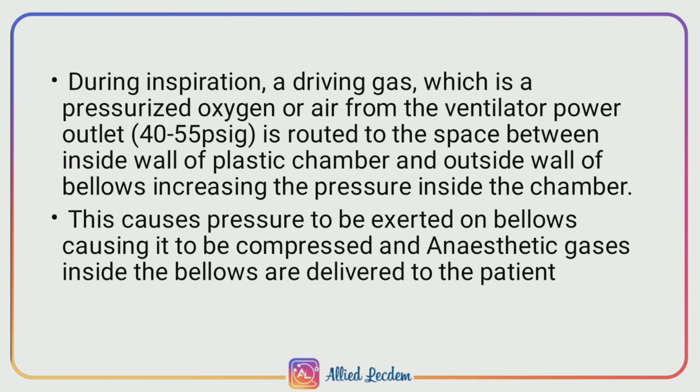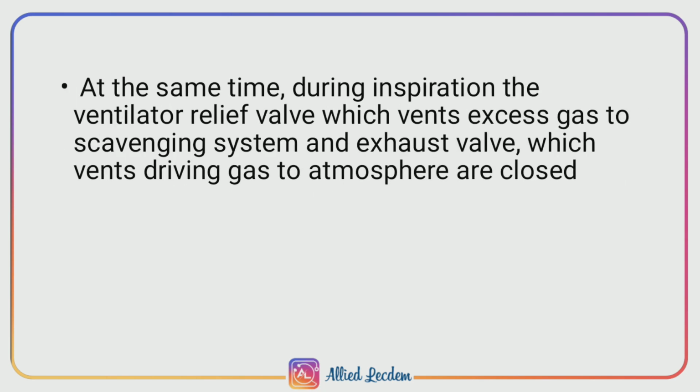The compression action is similar to the hand of an anesthesiologist squeezing the reservoir bag. At the same time, during inspiration, the ventilator relief valve, which vents excess gases to the scavenging system, and the exhaust valve, which vents driving gas to the atmosphere, are closed.